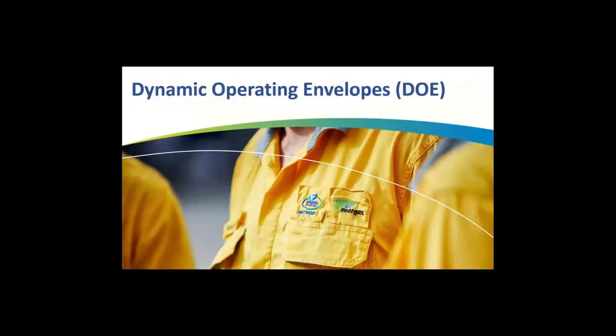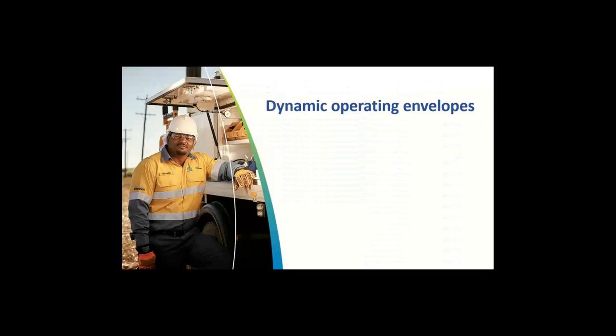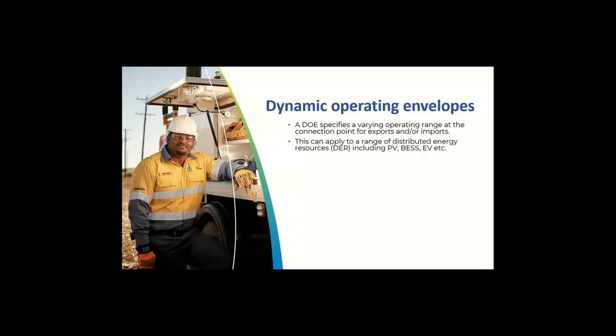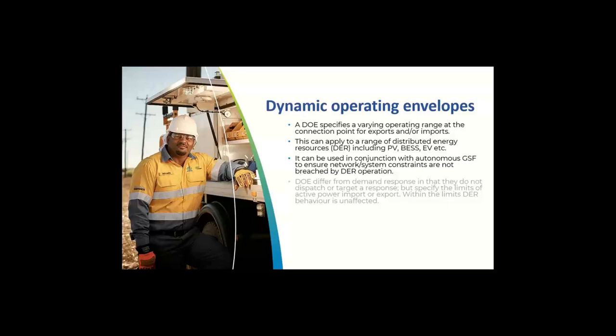The final development I wanted to share with you today relates to what has been termed dynamic operating envelopes in Australia. Dynamic operating envelopes, or DOEs, specify a varying operating range at the connection point for exports and imports through the connection point. They can apply to a range of distributed energy resources such as solar PV, batteries, and electric vehicles. And they can be used in conjunction with the autonomous grid support functions I mentioned previously to ensure network and system constraints are not breached by DER operation.